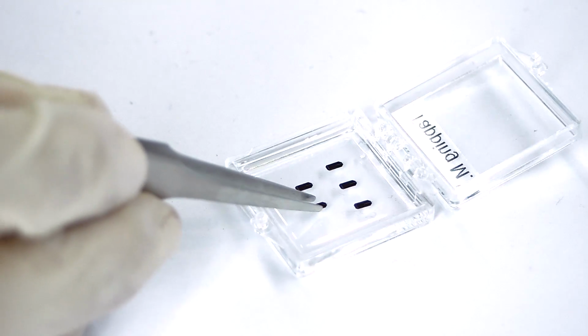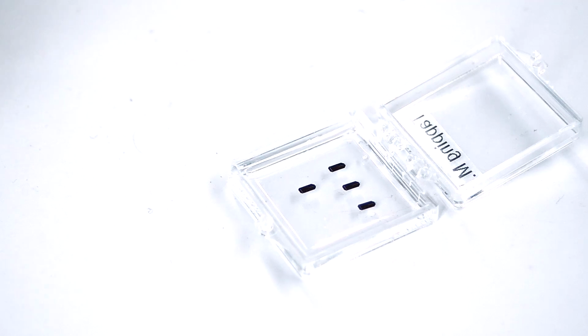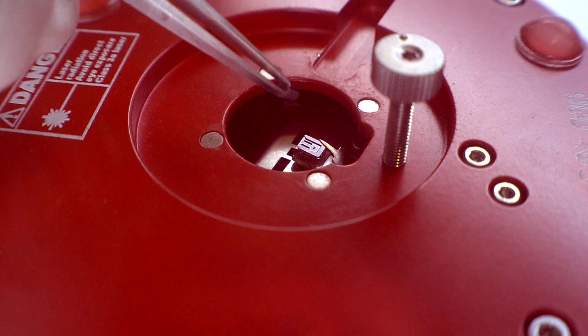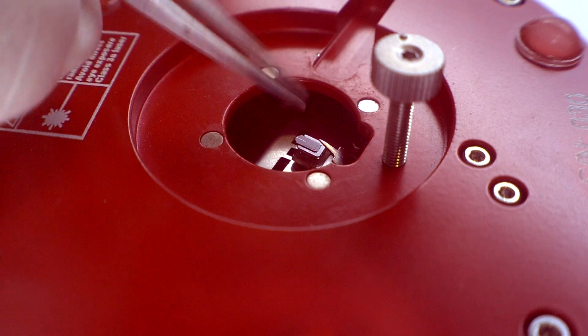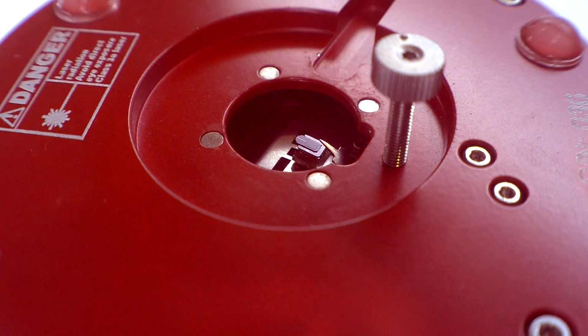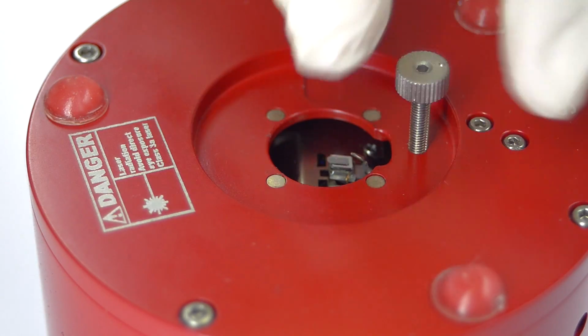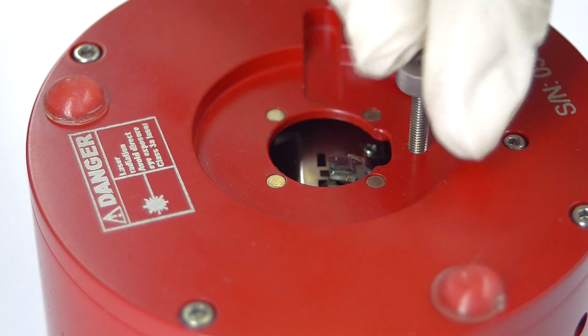Take a new self-aligning cantilever and place it on the cantilever holder, ensuring that it is seated on the slot on the holder. Tighten the thumb screw to re-engage the fulcrum.